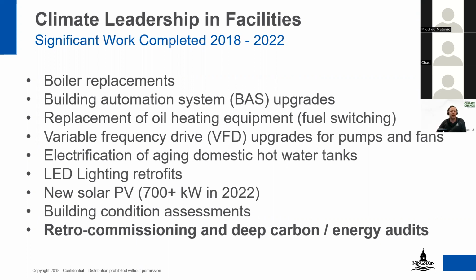Some other things not on this slide, to highlight how much we're trying to push the envelope: we're piloting a water treatment solution for heating and cooling systems that reduces the surface tension of water and increases heat transfer. We're also looking at an enzyme cleaning solution for heating and cooling coils on our HVAC systems that can reduce fan load through a dirty coil by up to 50%. We pilot these on one facility, make sure it works, functions, is safe and compliant, and then roll it out to the other 160 facilities we have.